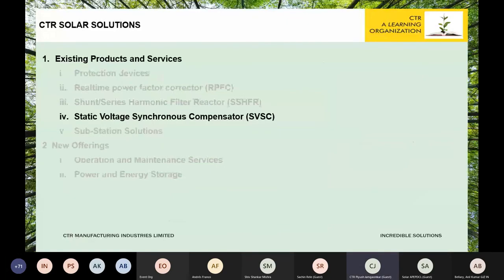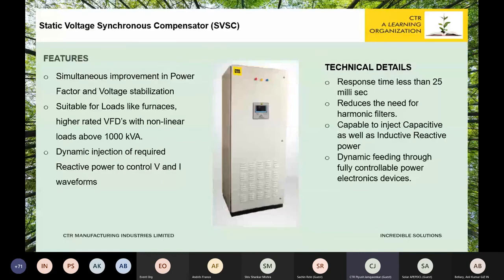Then we refer to the SVSCs, the static synchronous compensator or STATCOM. Apart from voltage stabilization in various loads, they are also used for stability improvement and PF. They sense, monitor and control the voltage and current waveform by injecting reactive power dynamically, connected in shunt with load and source. Whenever the reactive power demand increases, the STATCOM increases the output voltage and allows the reactive power to flow into the power source. Similarly, if the voltage has to go down, the voltage is reduced and the reactive power is absorbed to stabilize the voltage between the predefined set values.